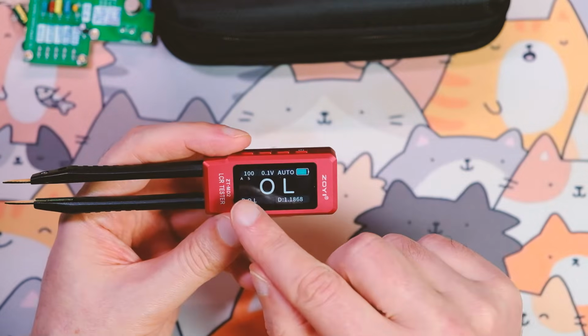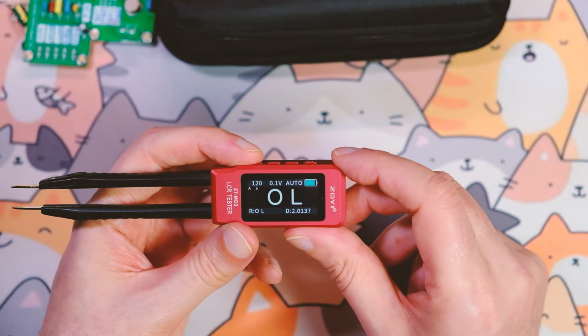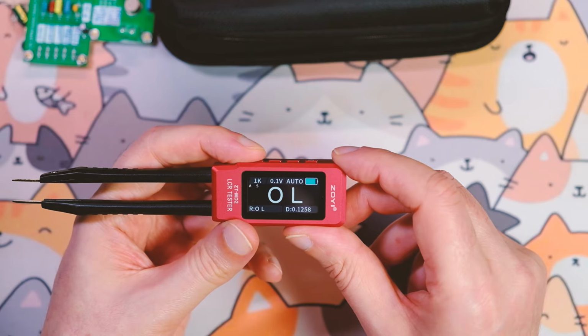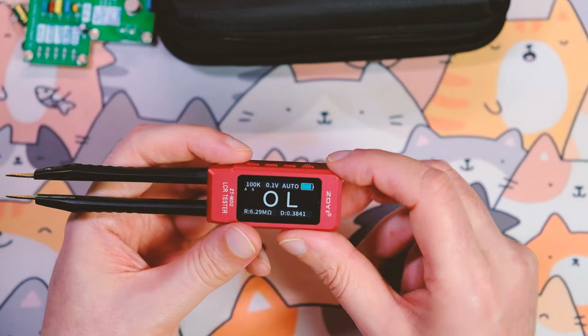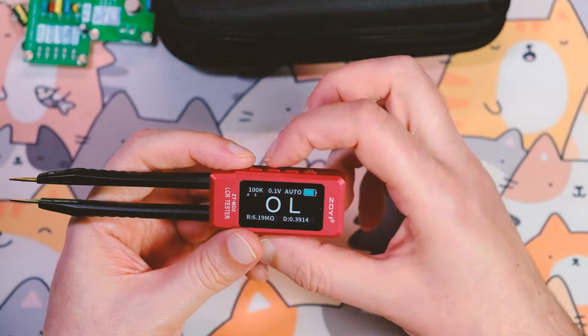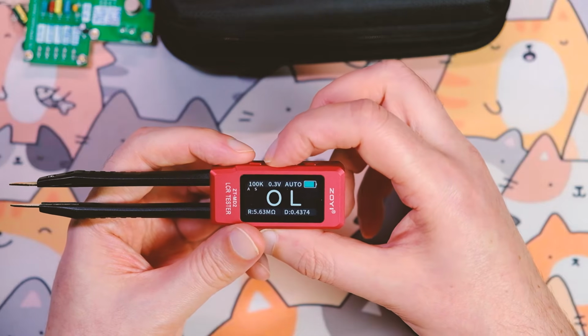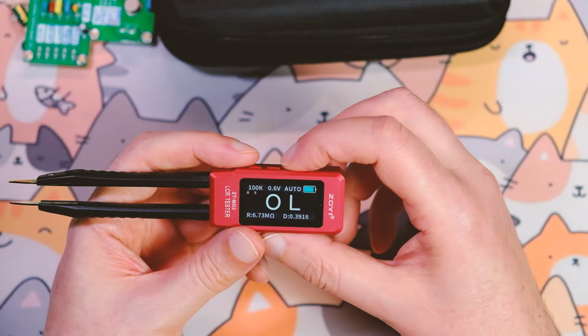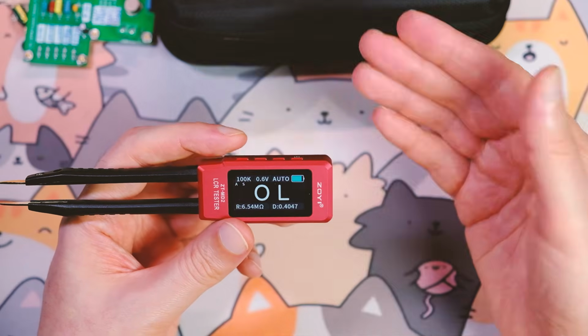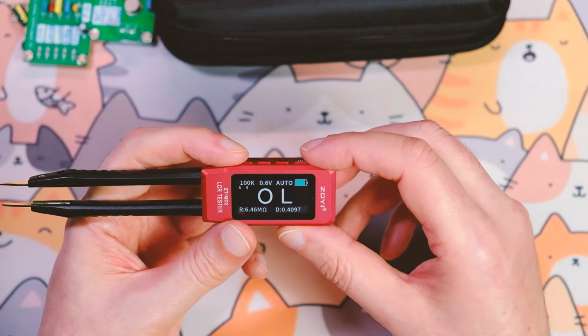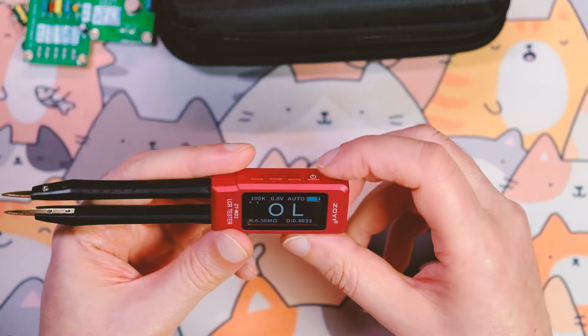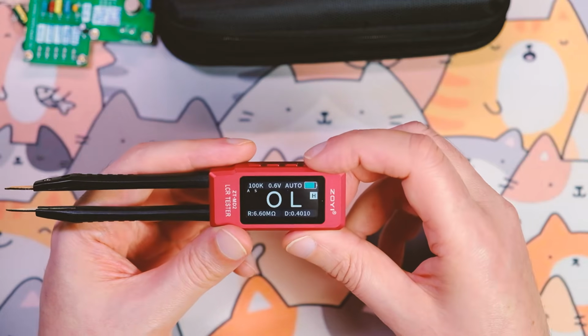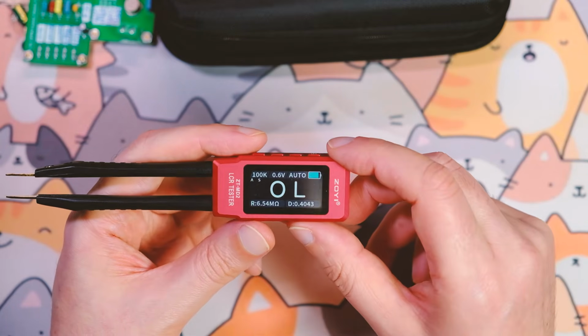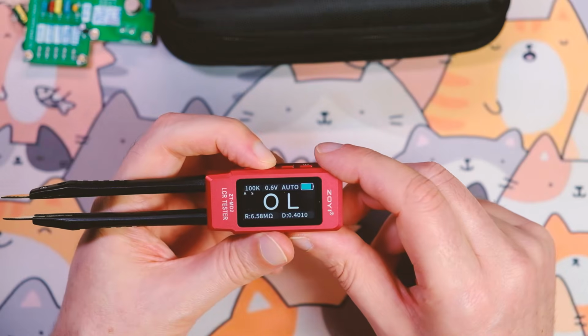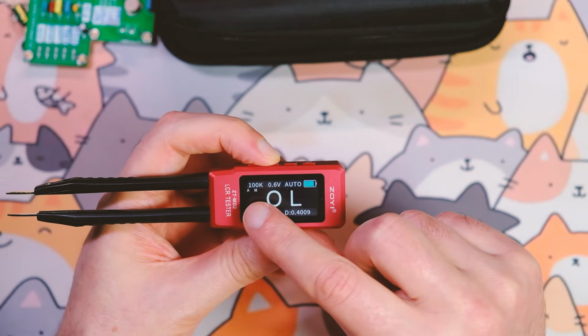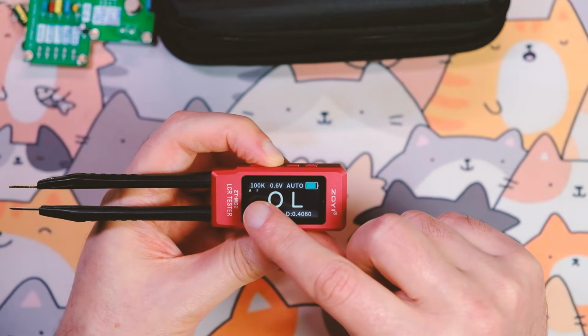In measurement mode, you can change the frequency 100 Hz, 120 Hz, 1 kHz, 10 kHz, and 100 kHz. You can also change the amplitude 100 mV, 300 mV, 600 mV. And you can select either automatic mode or specifically choose the parameters you plan to measure. To hold the data on the screen, press the power button. It's also the hold button. If you need to change the measurement speed, press and hold key 3. Medium speed, high speed, but I will perform all measurements at the low speed.